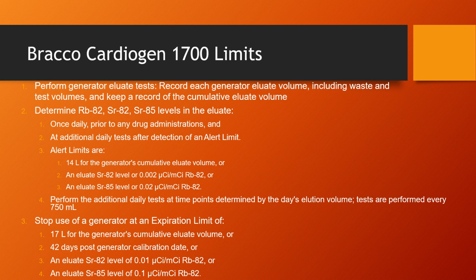So if any one of those conditions are met, then you have to perform the additional daily test at time points determined by the day's elution volume, and the tests need to be performed every 750 milliliters.